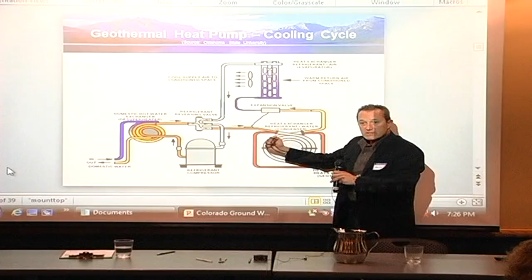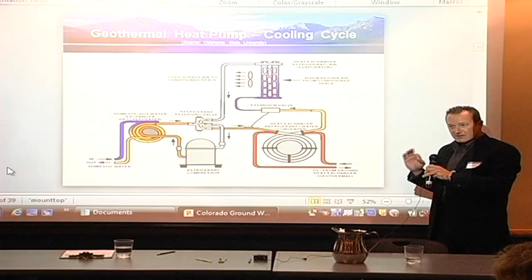into the loop field. Okay, so what we can see is during the heating season, we continually are drawing heat out of this water. We design our loop field temperatures to go no lower than 30 degrees in the wintertime. In the wintertime, we can get down to 45, 60 degrees is our sweet spot, if you will. In the summertime, on an extremely hot summer, a couple months, we continue to dump heat in the loop field. That loop field water can get up as high as 90 degrees at design temperatures. So you can see there's quite a bit of fluctuation.